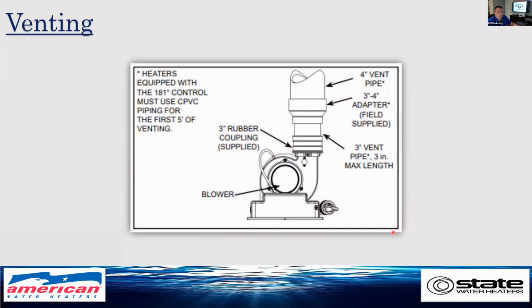In the venting, when we need to upsize the venting to accommodate the equivalent feet that we're running, an adapter or bell coupling needs to be installed as close to the blower as possible. So here we're upsizing from 3 inch to 4 inch. In doing so, we need to supply a 3x4 adapter here, or bell coupling is what I call it. And if you look here, a 3-inch vent pipe, 3-inch max length, meaning we need to have that pipe as close to that blower as possible. Meaning you can't run your 6 inches, put a 3-inch 90, and then upsize. That's not correct.